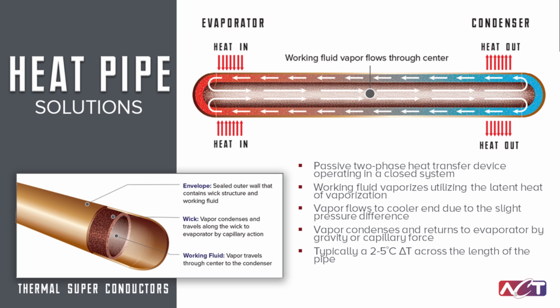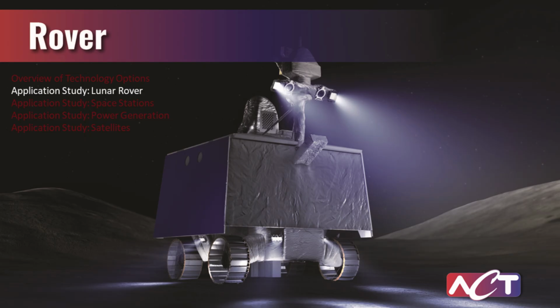Where it's colder or connected with a heat sink, it'll give up its latent heat, condense back to a liquid, and be absorbed in a wick structure that surrounds the inner diameter of a heat pipe, and that wick structure will passively pump the liquid back to the heated section. So this is a fairly simple version of a heat pipe, and as we've discussed, there's many different variants, and you can have multiple heat sources, but just to give an idea of what's going on internally, it's all driven on the principles of two-phase heat transfer.